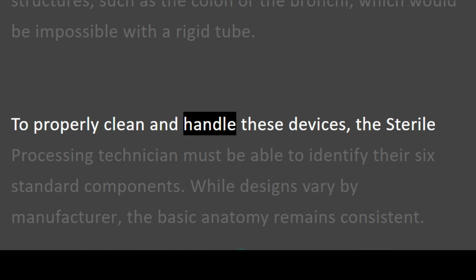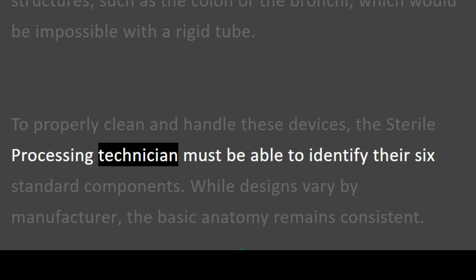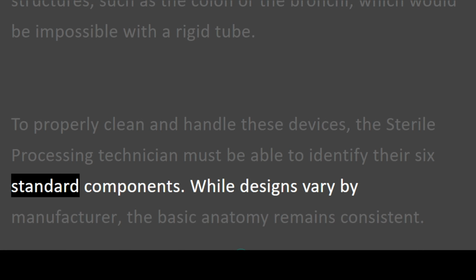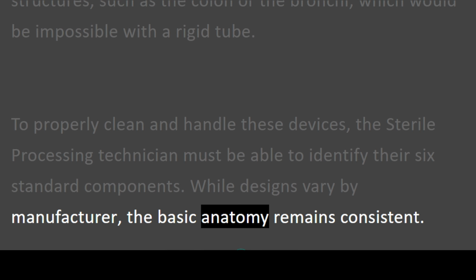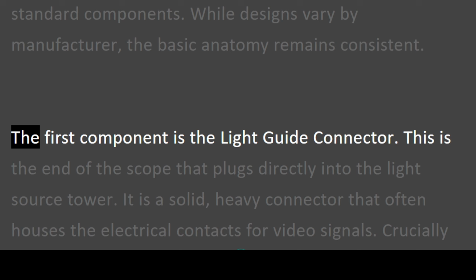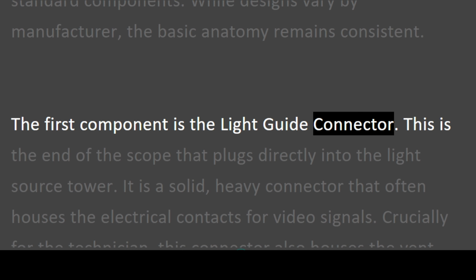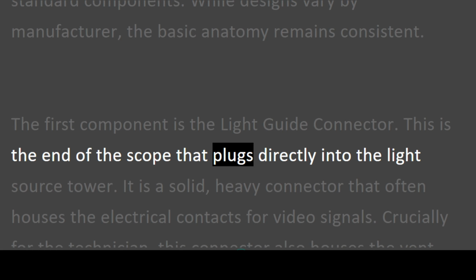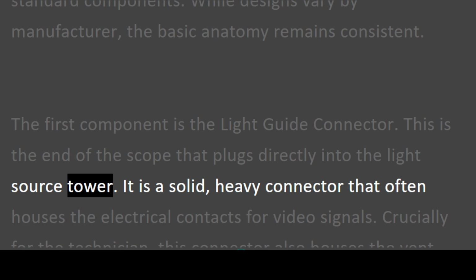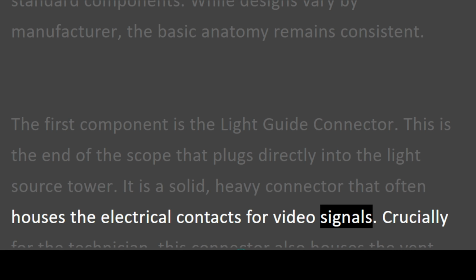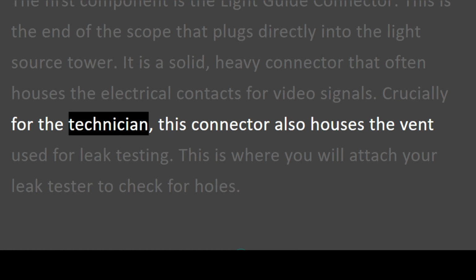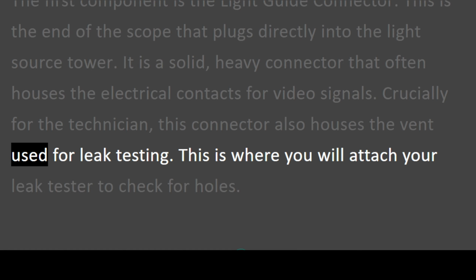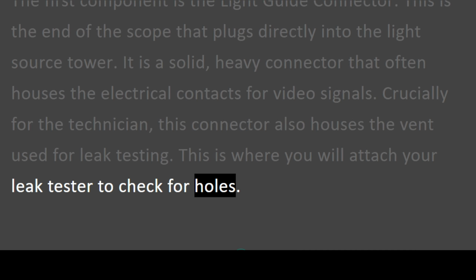To properly clean and handle these devices, the sterile processing technician must be able to identify their 6 standard components. While designs vary by manufacturer, the basic anatomy remains consistent. The first component is the light guide connector. This is the end of the scope that plugs directly into the light source tower. It is a solid, heavy connector that often houses the electrical contacts for video signals. Crucially for the technician, this connector also houses the vent used for leak testing. This is where you will attach your leak tester to check for holes.